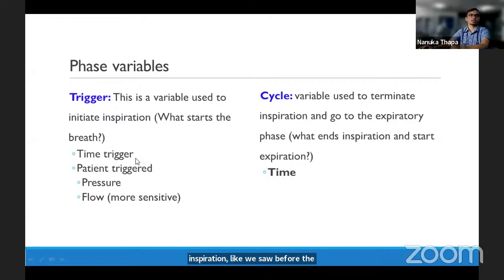It can be a time trigger. Suppose in 1 second, we said that the inspiration is 0.5 seconds and the expiration is 0.5 seconds. So after 0.5 seconds of inspiration, then expiration will start. And after 0.5 seconds of expiration, inspiration will start. It can be time triggered, it can be pressure triggered.